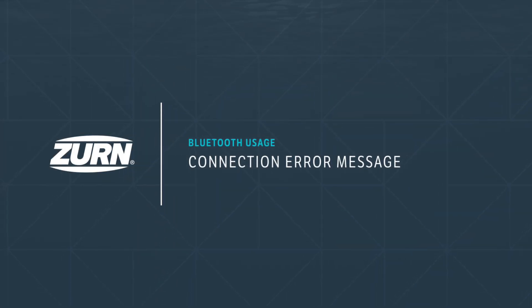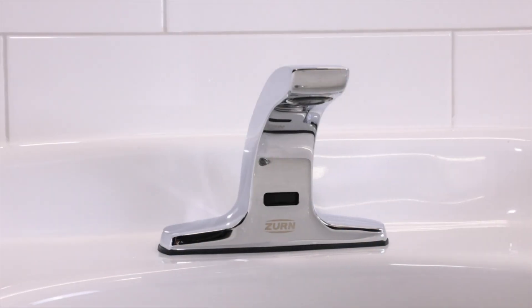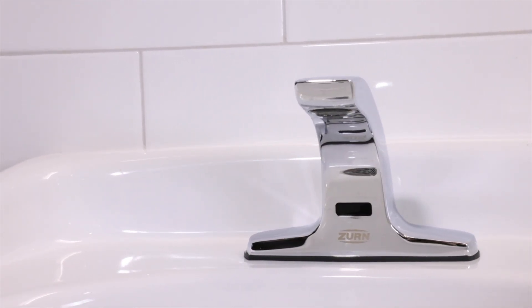Connection error message. If multiple Zurn devices are beaconing all at the same time, you'll receive an error message in the app. If this happens, you will not be able to connect to Bluetooth. First, determine which faucets are beaconing and activate them by waving your hand in front of the sensor so the faucet turns on. This will take the faucet out of Bluetooth mode.